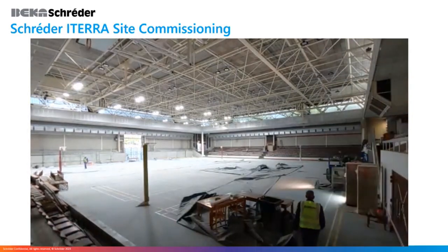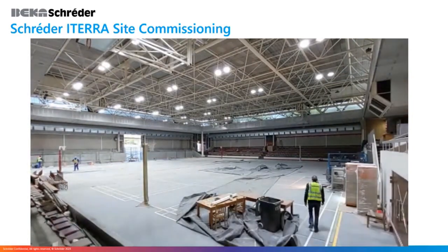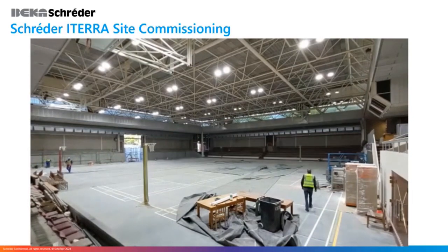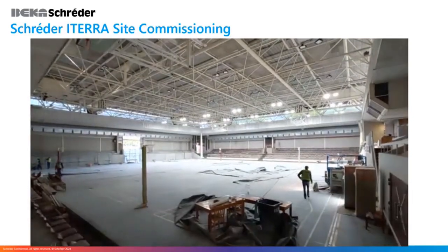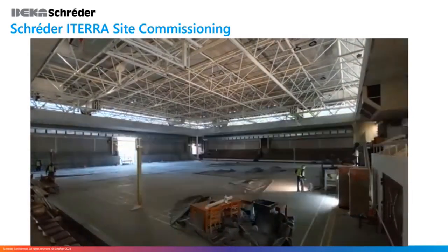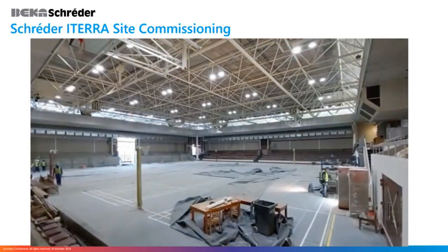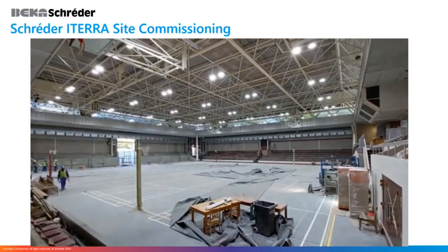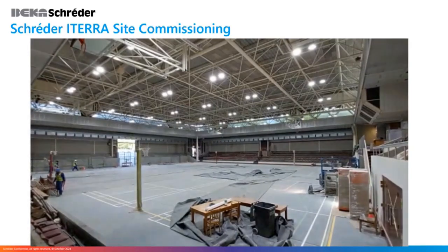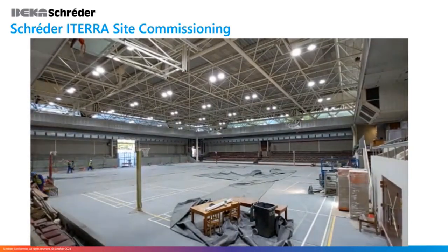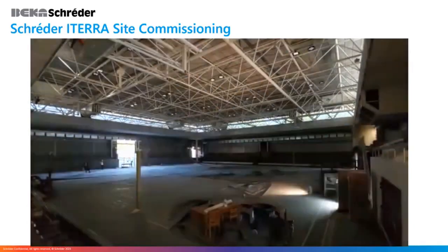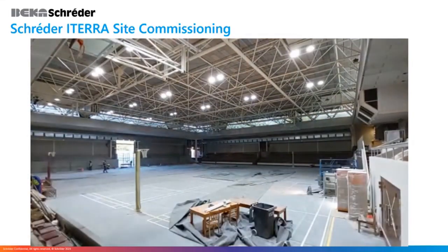It has to do with the power consumption of the driver to the control system. Therefore, in a design, we can connect 8 drivers to one node, and we can then individually control those luminaires. Every single one of those 8 luminaires can be controlled.